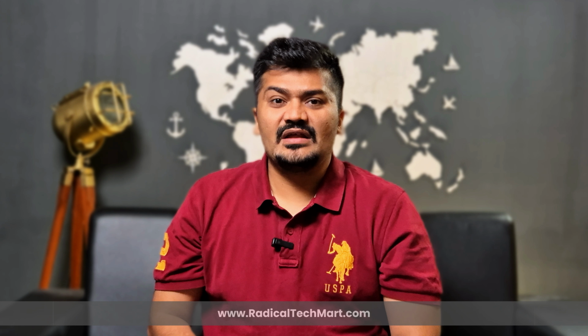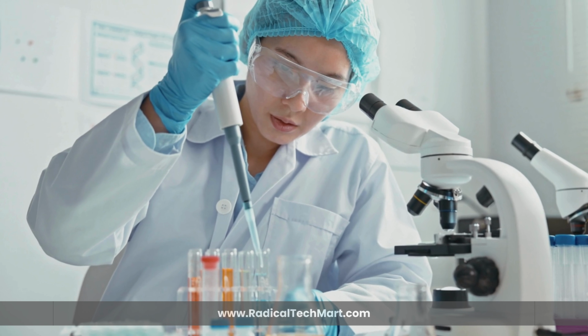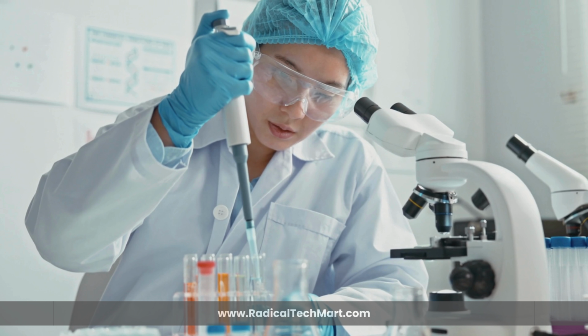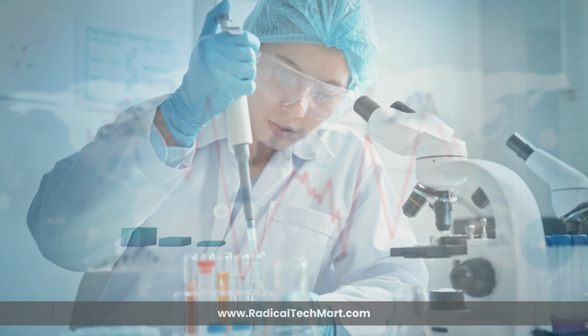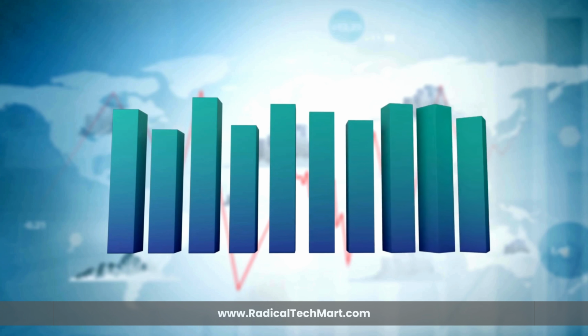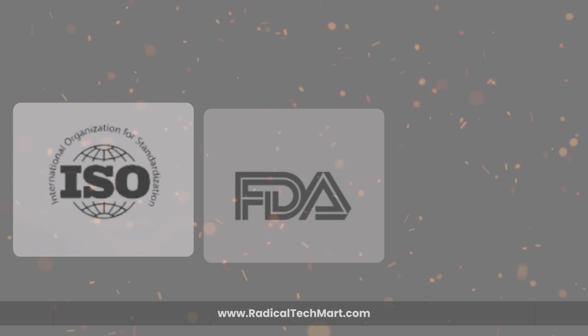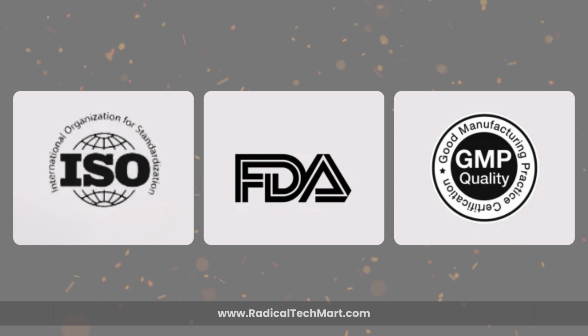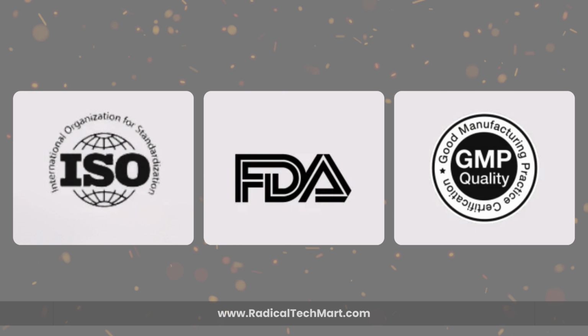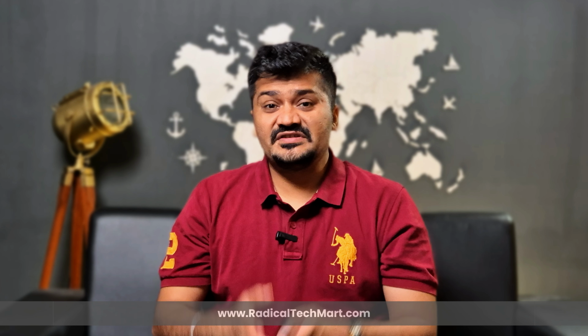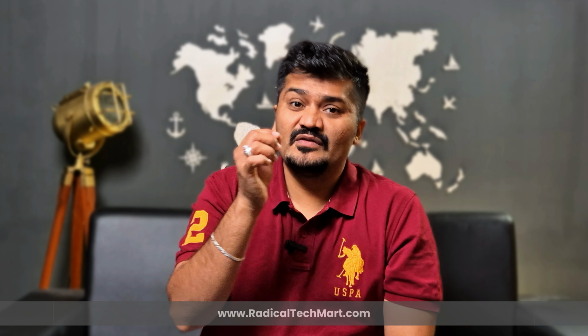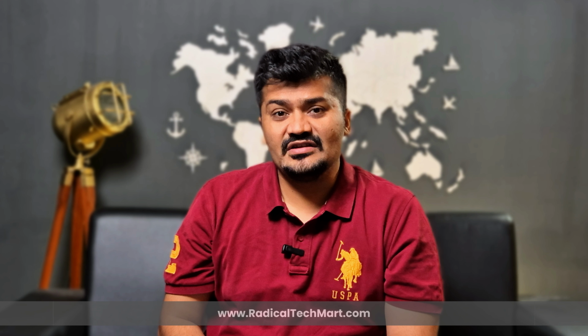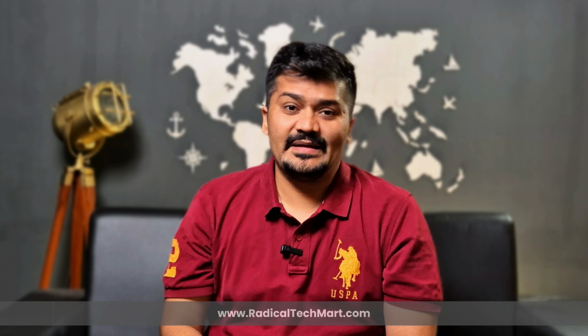Now let's cover external or certified calibration. It is a lab-based calibration process, widely used by climate chambers where traceable standards are needed. It is highly accurate and comes with certification. It is required for ISO 17025, FDA, WHO, or GMP environments. For mission critical operations, it's always better to rely on external calibration with certified labs.